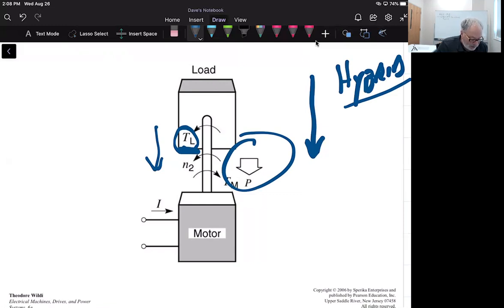The steady state speed depends upon whether the motor torque was greater or less for a certain period of time before the actual steady state conditions. And he says, whenever the motor torque and load torque are not exactly equal and opposite, the speed will change. The rate of change depends upon the inertia of the rotating parts, and we'll look more at that in some detail in some upcoming sections.